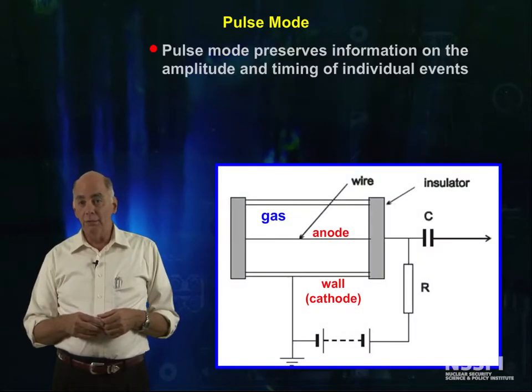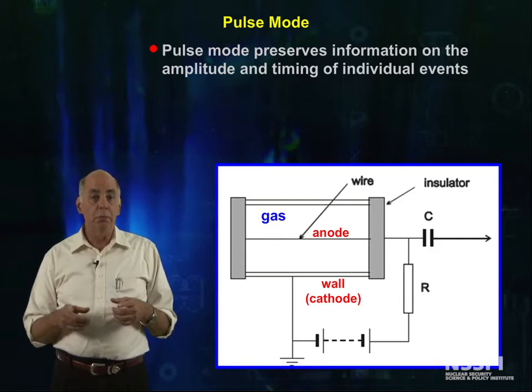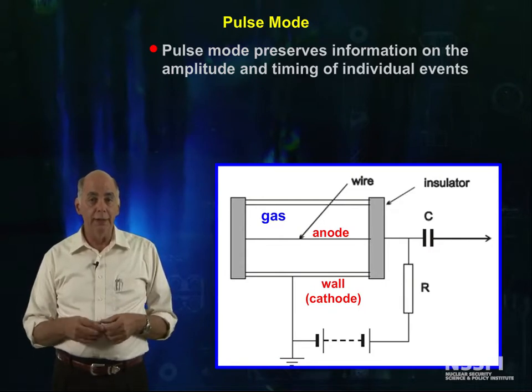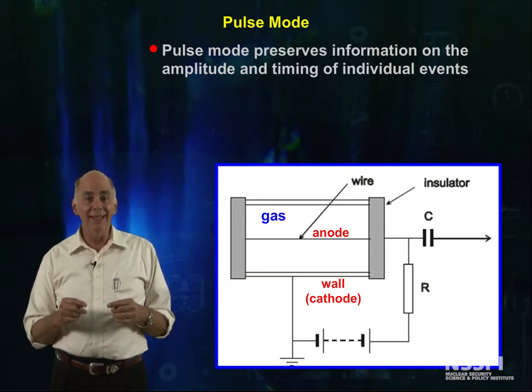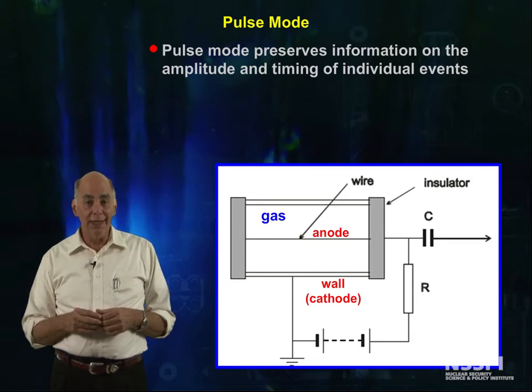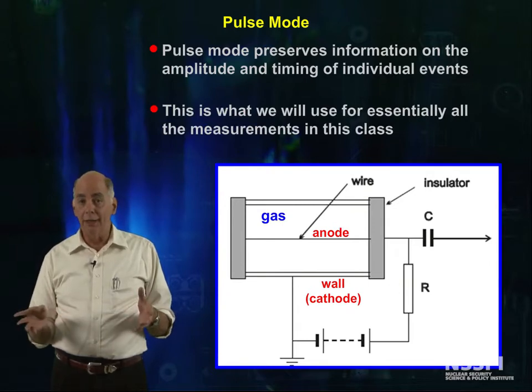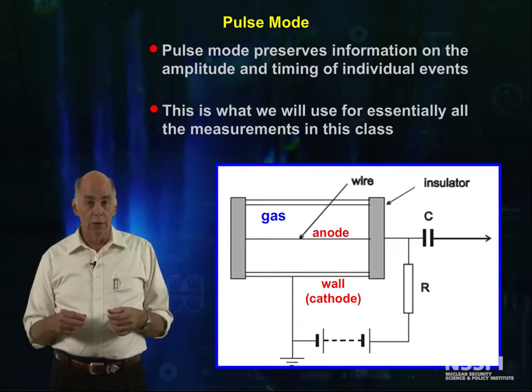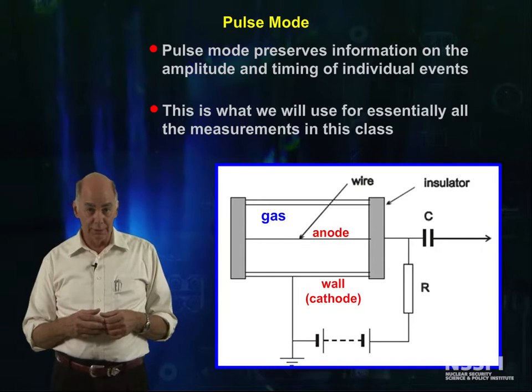For identification of nuclides, current mode is no good. We use pulse mode, the other way to monitor the signal coming from the detector. We look at the signal in detail that comes from each ionizing event in the detector. All the instruments used in this class will be operated in pulse mode because it preserves the information on the amplitude and timing of individual signals.